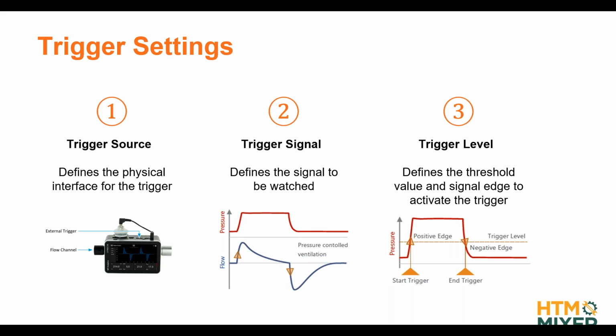Not happening very often, but some ventilator manufacturers have that. Typically, you have your flow measurement or pressure measurement, and then in the trigger signal, you need to define which signal should be used for triggering. Typically, it's flow or pressure. Okay, and then the trigger level finally defines on our curve, on our waveform that we selected, at what threshold should the trigger be activated. And beside the actual threshold value, we also have to specify should it be triggered when we are on a rising edge of our signal or a falling edge of our signal. Okay, does that make sense?